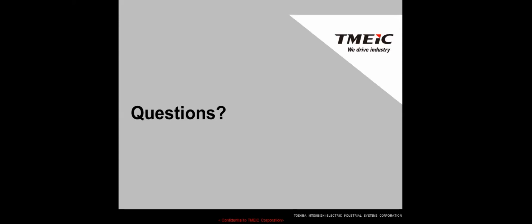Are there modeling tools available for ETAP or SKM? Thanks. Modeling tools. I know ETAP and SKM are power systems modeling software. In terms of what tools we have on there, I'm going to probably say no, although I might be wrong. I'm not sure really what modeling tools you need. With all drives, even regenerative drives, they do not put power back on a power system in time of a fault. For instance, if you have a fault on a motor, then that motor can feed back into the fault. But if you have a fault on a drive, even if it's regenerative, it doesn't do that.